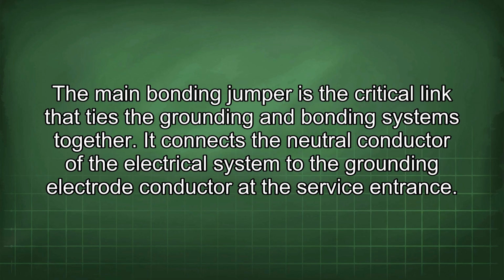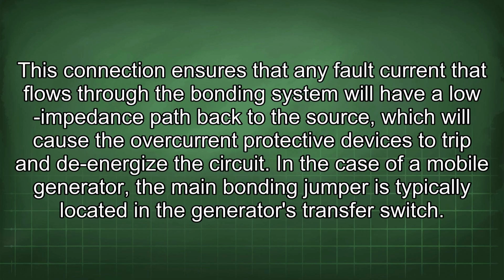It connects the neutral conductor of the electrical system to the grounding electrode conductor at the service entrance. This connection ensures that any fault current that flows through the bonding system will have a low impedance path back to the source, which will cause the overcurrent protective devices to trip and de-energize the circuit.